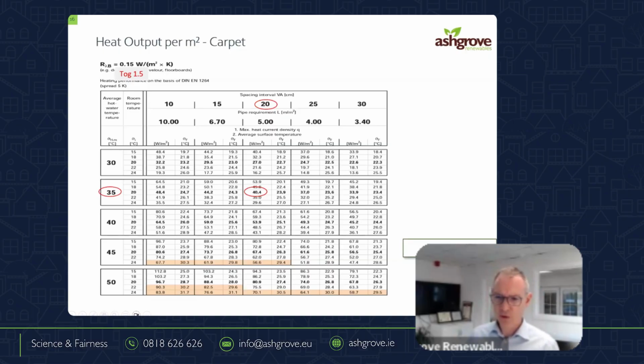So if I want to produce 100 watts, and I have a carpet, I now have to go to 50 degrees here that you can see down here in the bottom. And if the pipes are at 20 centimeter spacings in the ground, I can get 80 watts. So I now can't heat the room. If I go to 6-inch centers, which would typically be the fix-all in Ireland, we've designed it, which means I put it in at 6 inches, but I didn't think any more about it, 88 watts. And if I put it in at 4-inch centers, which we practically never see in Ireland out in the industry, 96.7 watts. Now that will get me to 20 degrees.